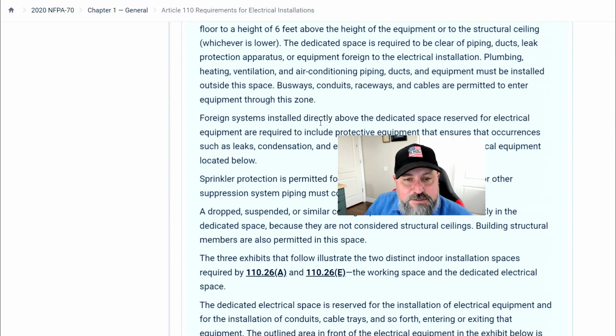Foreign systems installed directly above the dedicated space reserved for electrical equipment are required to include protective equipment that ensures that occurrences such as leaks, condensation, and even breaks do not damage the electrical equipment located below. So that's if you have anything above it, outside that 6 feet, and it's going directly above the equipment, they have to have special protection from leaks and put that into place on their equipment.